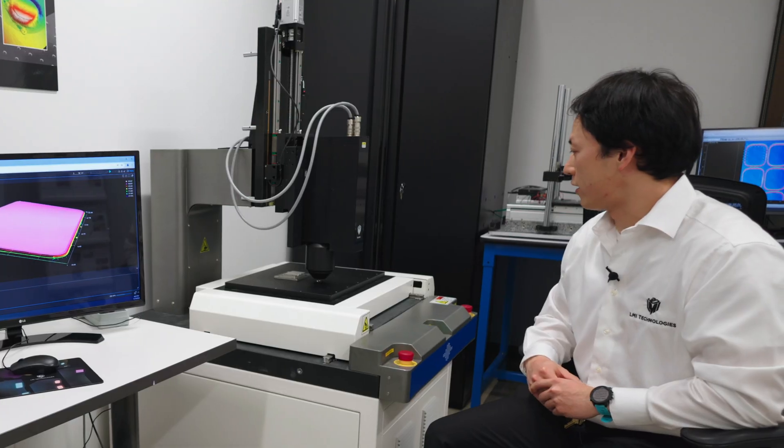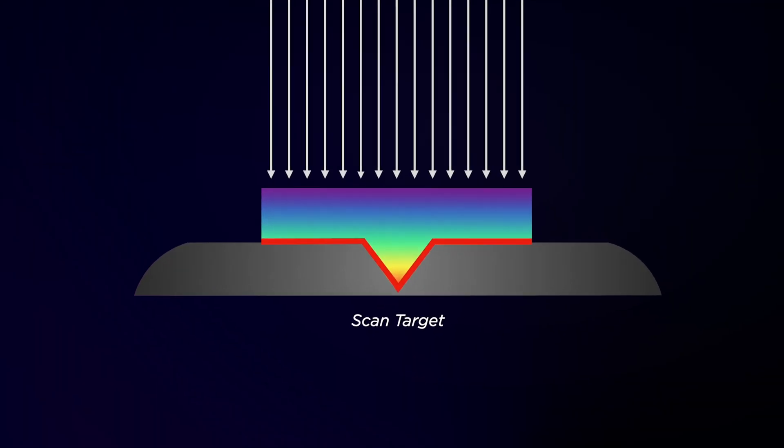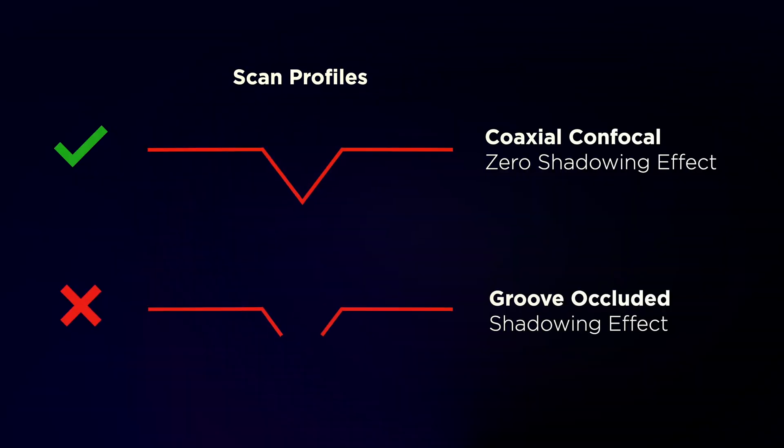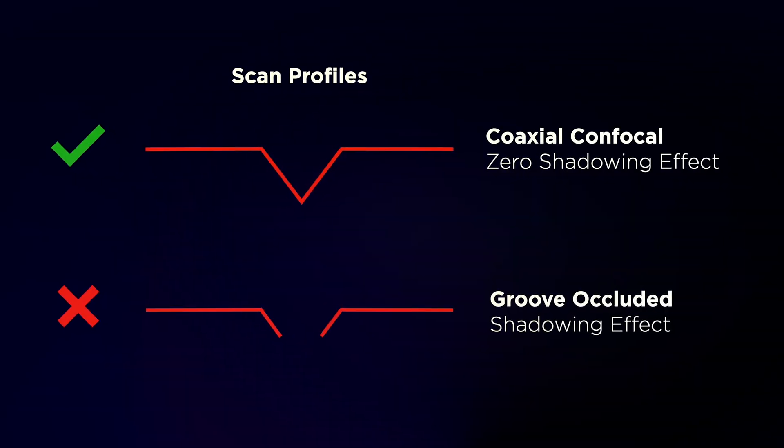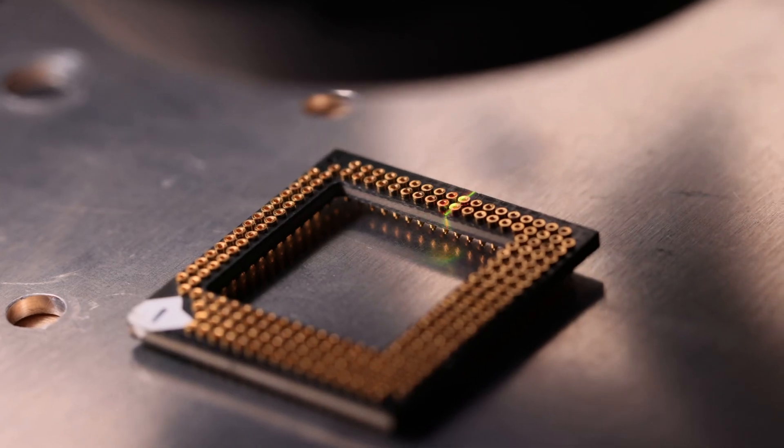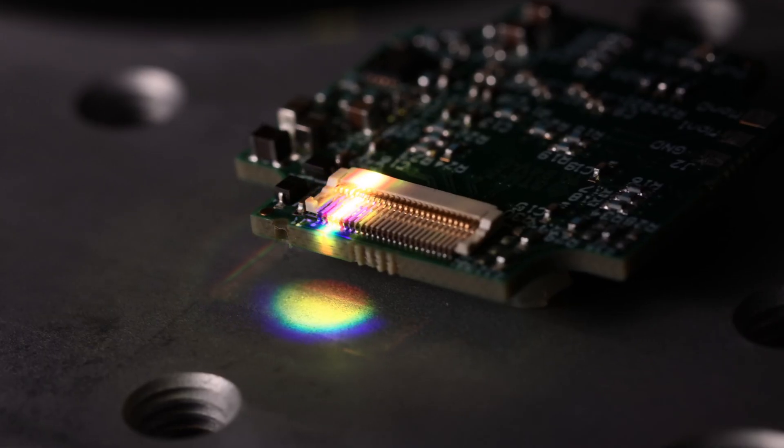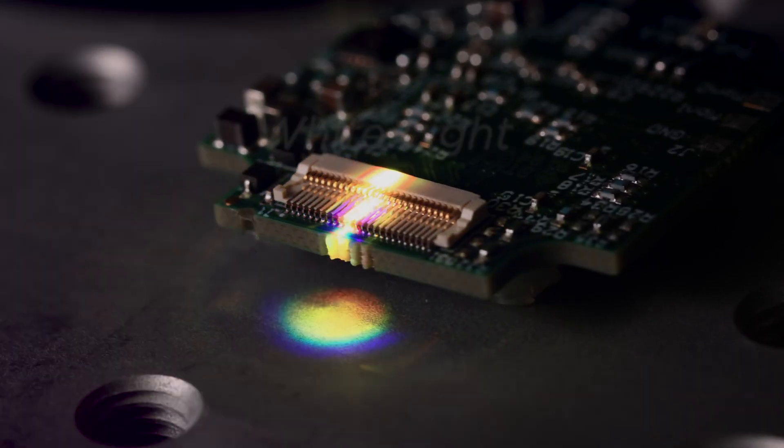Here this is the GoCator 4010 sensor - it's the coaxial confocal sensor. Working distance is about 9mm. Resolution is about 1.9 microns. This is the highest resolution confocal sensor that we have.